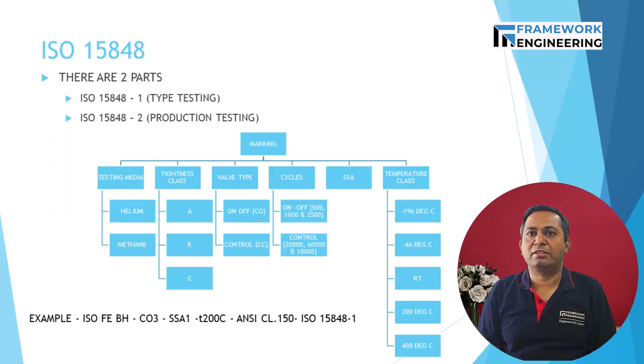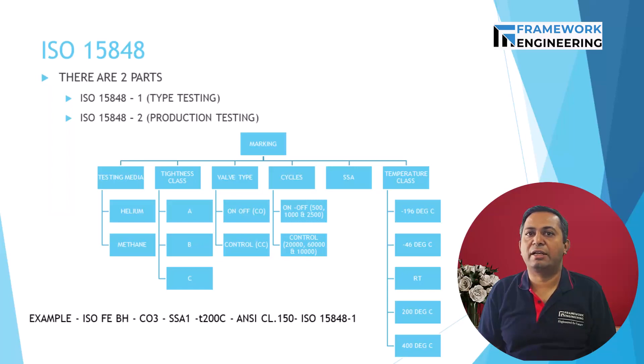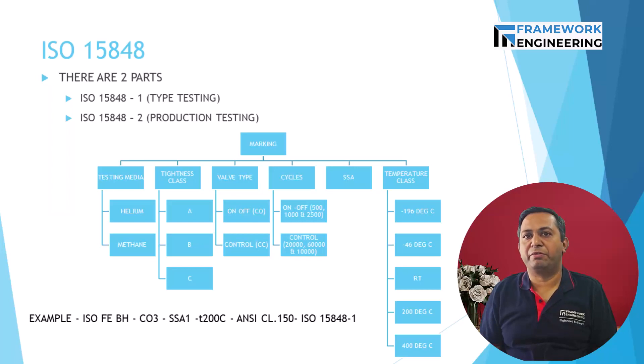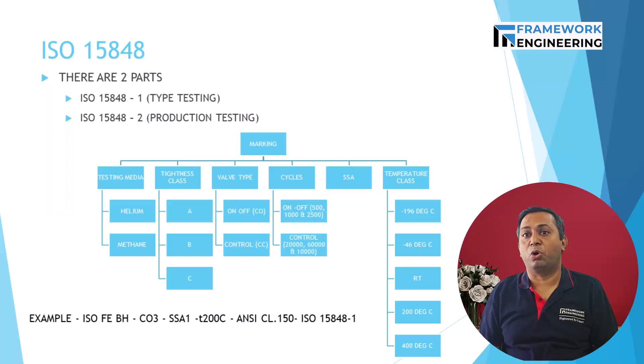In production testing — that is ISO 15848-2 — one valve per valve type, pressure class, and size is considered for testing. A sniffing test is used as per Annexure B of the standard. Test pressure is around 6 bar and the leakage is expressed in PPM. The valve is cycled 5 times and then placed half open to perform the testing. If testing fails, the whole batch is rejected. For tightness: Class A means less than 50 PPM, Class B means between 50 and 100 PPM, and Class C means between 100 and 1000 PPM, for the stem seal. For the body seal, it must be less than 50 PPM for all classes.